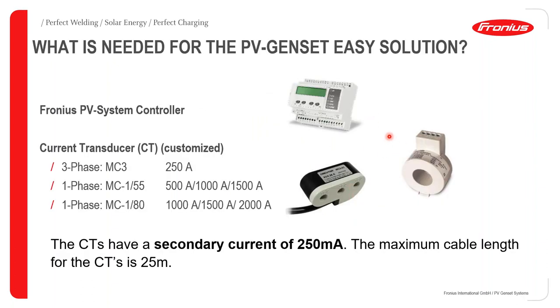For the PV Genset EZ solution, the key components are the PV system controller and the current transducers. These are available in three variations: a three-phase CT measuring up to 250 amps; single-phase CTs — the MC1/55 — measuring from 500 to 1,500 amps; and single-phase CTs — the MC1/80 — measuring from 1,000 to 2,000 amps. The CTs have a secondary current of about 250 milliamps, and the maximum cable length to the PV system controller is 25 meters.